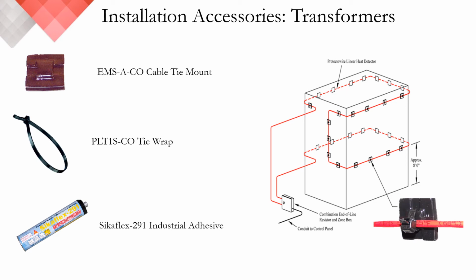In addition, or in place of installation on the deluge pipes, the linear detector can be applied directly to the transformer for early detection of overheating. Here, we illustrate the proper techniques to apply the detector. As you'll notice, we don't want to make any kind of penetrations directly into the transformer. Rather, we want to work with the appropriate cable tie mounts that can be adhered directly to the surface of the transformer with an industrial adhesive. We recommend Sikaflex 291. In addition to the close proximity, the linear detector's outer jacket options permit the installation in a wide range of environments from -60 degrees Fahrenheit or -51 degrees Celsius to as high as 392 degrees Fahrenheit or 200 degrees Celsius.